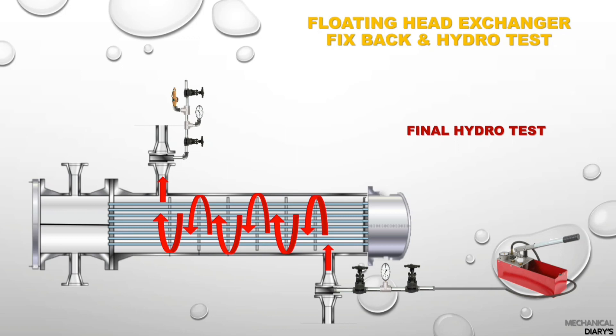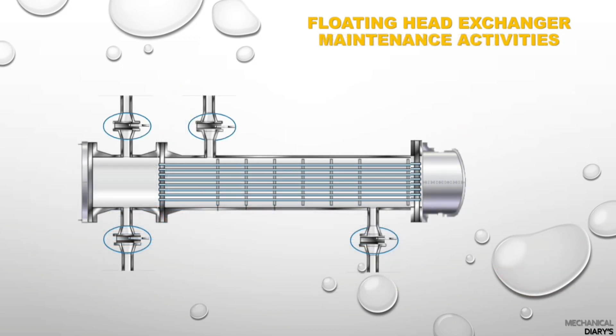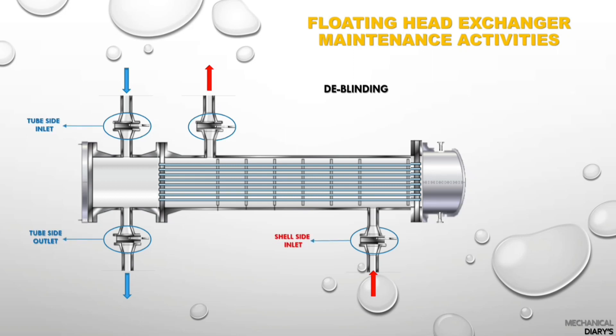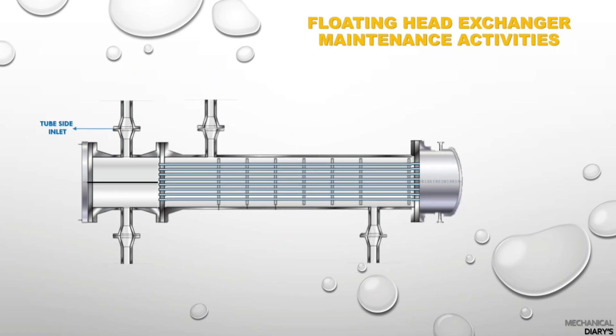Get clearance from operations and proceed to the next activity: de-blinding. As mentioned earlier, blinding starts from the inlet, so de-blinding should start from the outlet only — this reduces risk. After de-blinding, hand over the equipment to operations. If the exchanger feed is hydrocarbon or hydrogen, operations will first perform nitrogen purging before introducing feed to the exchanger.